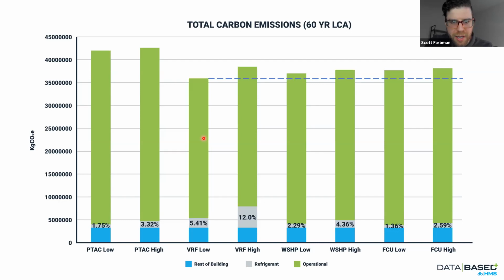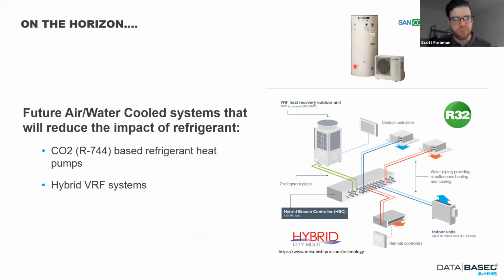Now, I just want to show you what I had already said. So on the low end, how things stack up, and on the high end, how things stack up. Some may argue that VRF on the high end might not be a significant difference, but I think it's something we need to consider. So what's on the horizon? And this is where I was going with different types of refrigerant. Up here on the top right, we have the Sanden heat pump water heater. This is using CO2 as a refrigerant. So if you remember, that's got a global warming potential of 1 instead of 2,000. So right off the bat, you're really limiting the impact the refrigerant has on this one system.